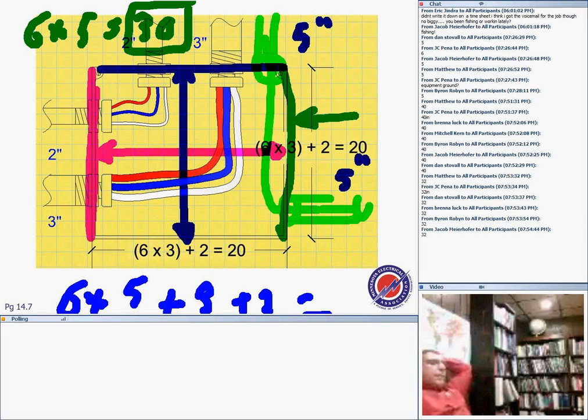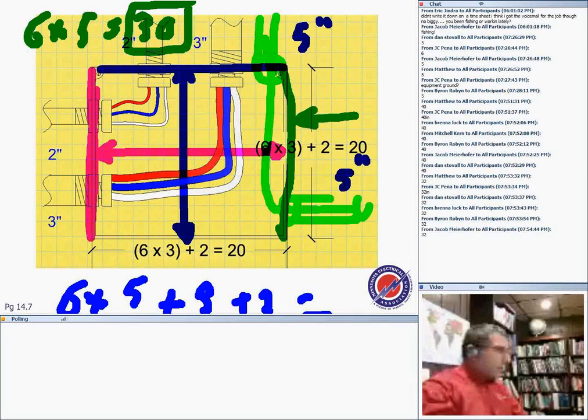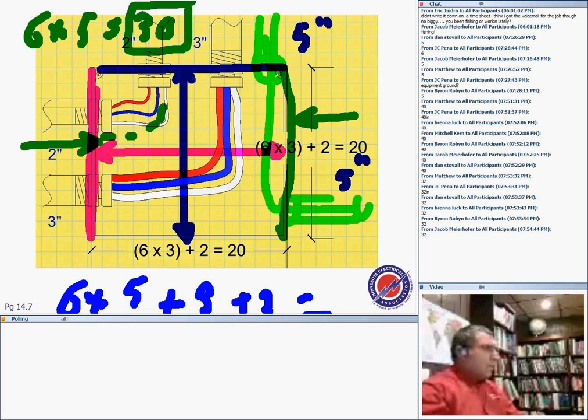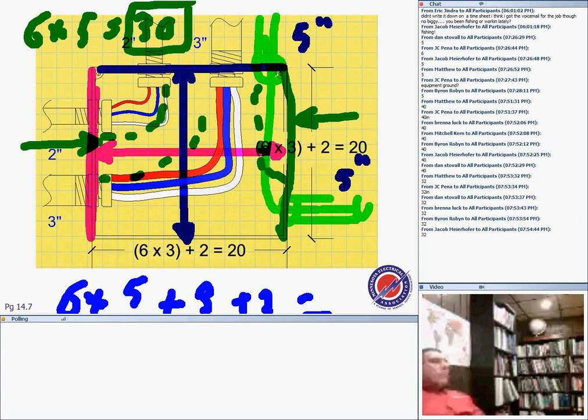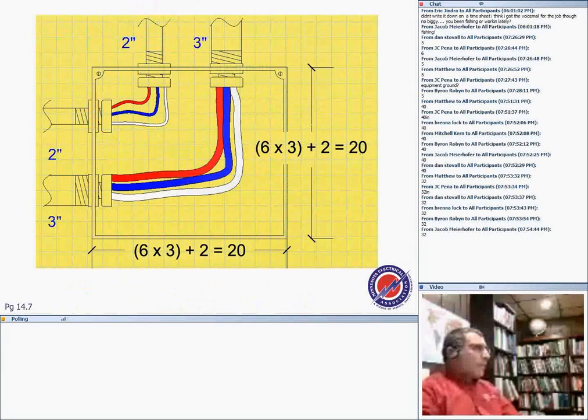This would be 30 by 35. Question about this: see how the first application gave us 20, but we went to the other wall, and because this is going up, it gives us a U-pull. So my box now is 30 by 35. Any question, guys? See, adding that conduit changed the whole dimension of this box.